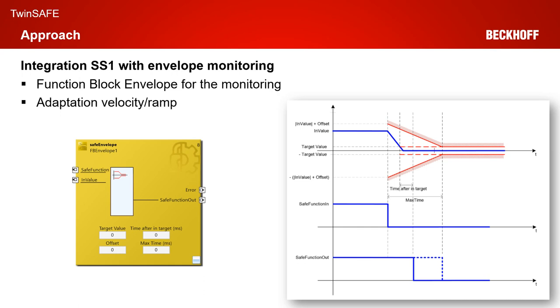We use the function block Envelope to create our ramp monitoring. The function block has four parameters shown in the left picture, and I also included the function block diagram in the right-hand corner. The Envelope function block creates an envelope from the absolute value of the input. As long as the input value stays within the envelope, the function block output is true. If it violates the envelope, the output goes to false.